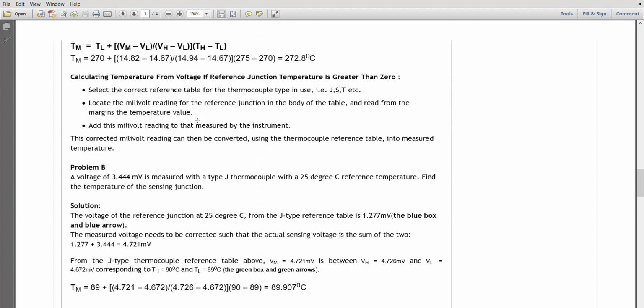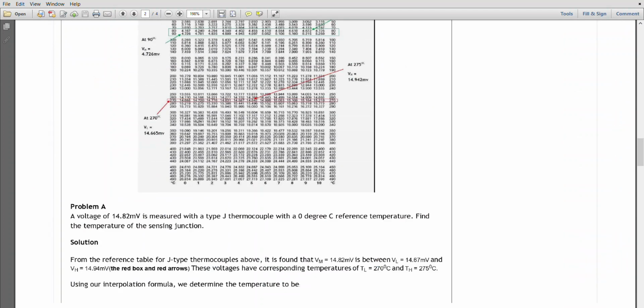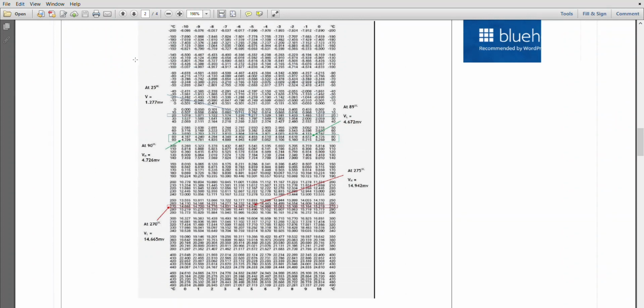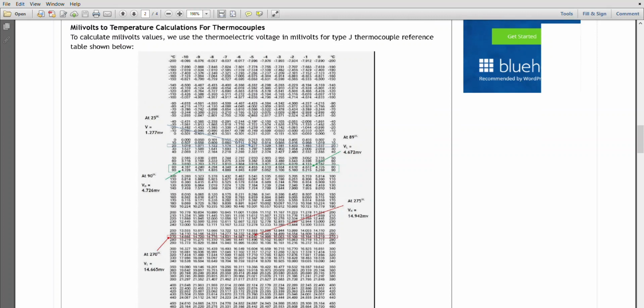Okay, so the question most of the time is how to go for the cold junction compensation. In industry, how they have done it so far is they have calibrated, they have a chart. The chart is called temperature and thermo EMF chart. How this chart looks, the chart looks something like this. The left column is temperatures, and the middle one is thermo EMF in millivolts. This thermo EMF will be corresponding to a temperature.